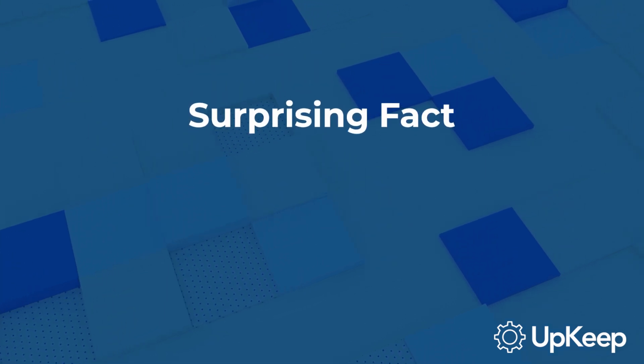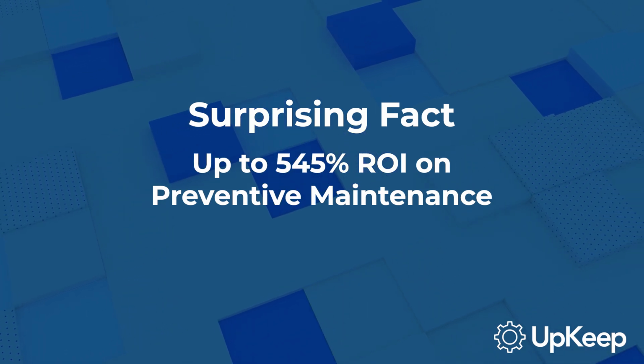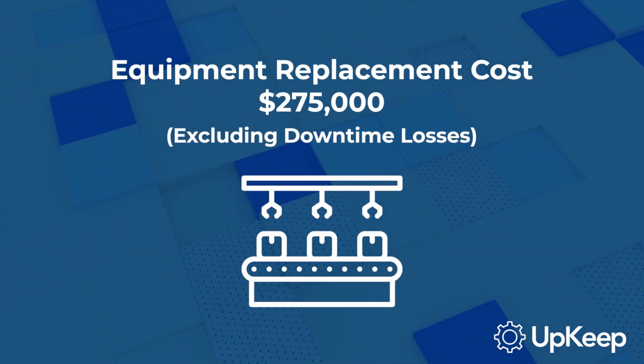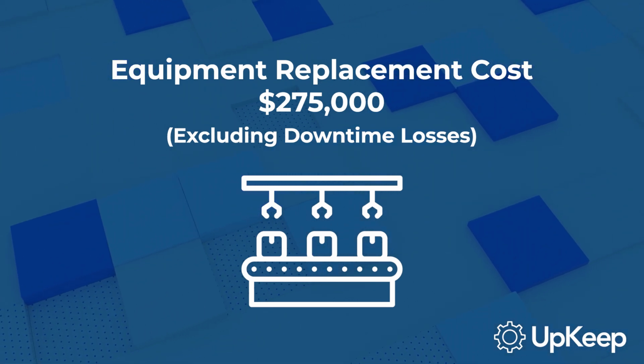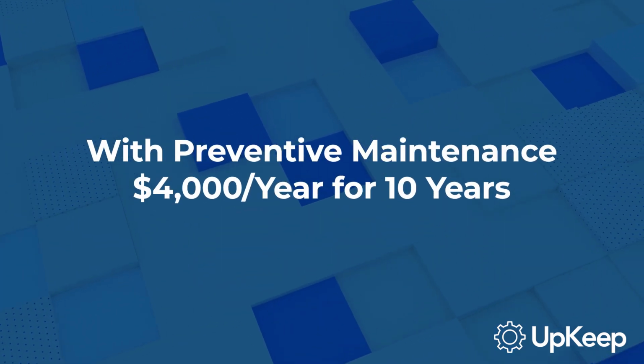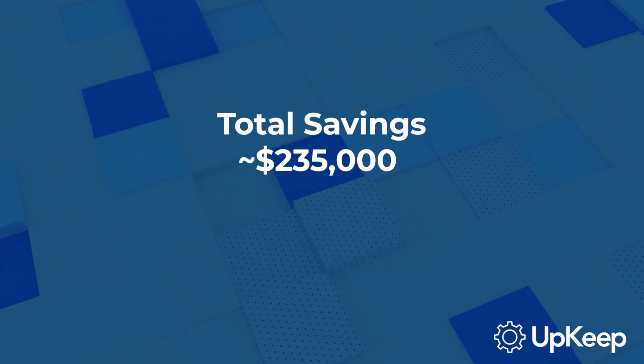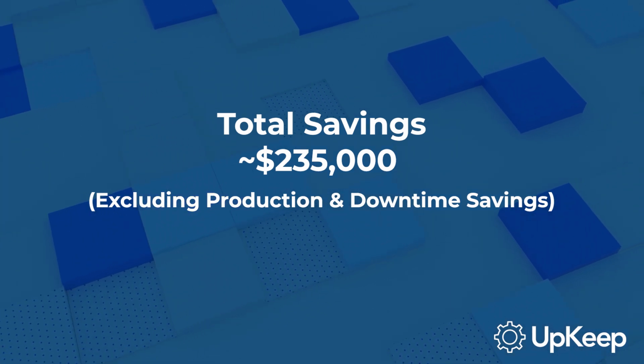Here's a fact that might surprise you. Well-developed preventive maintenance plans offer up to a 545% return on investment. This means that each dollar spent on preventive maintenance saves $5 or more in the future. Let's consider a vital piece of equipment that costs $275,000 to replace, not including the lost revenue from production downtime. Without maintenance, it may last 5 years. But with preventive maintenance that costs $4,000 per year, the machinery can last up to 10 years. The total savings over 10 years would be close to $235,000. Not including the savings from continued production and lack of downtime.